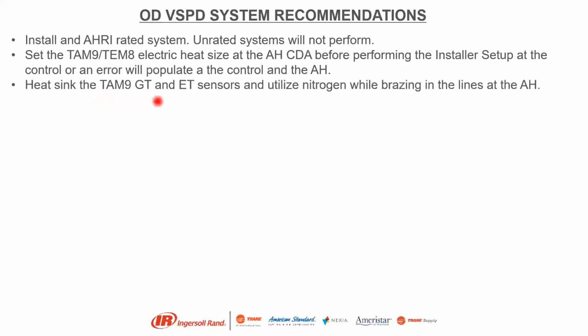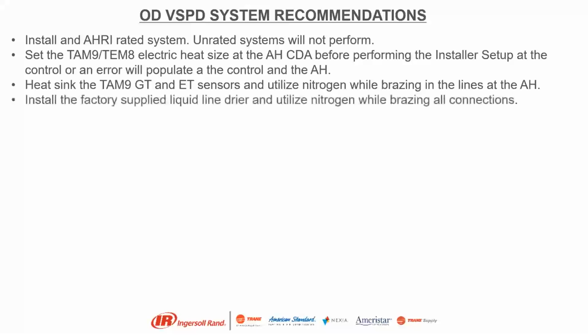Heat sink the TAM9 GT and ET sensors and utilize nitrogen when brazing. So that means our sensors in the TAM9 on the coils where you're going to braze, you're going to disconnect those from the actual line. So when you're heating that up with nitrogen, you're not cooking that sensor. We still get calls on it. The guys cooking that sensor, and we can tell if it's not going to read correctly. So you're going to have to automatically change out that sensor.